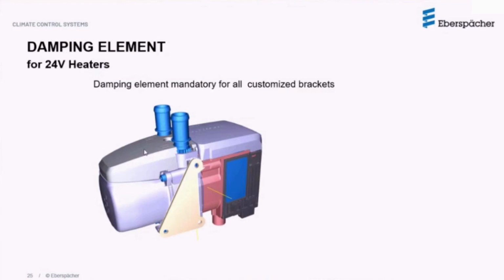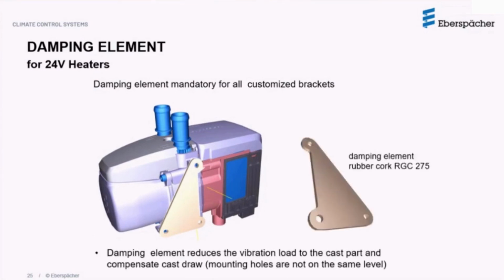With the 24-volt version of the Hydronic S3 heaters, there is what's called a damping element. This is required for all installations, and its purpose is to reduce the vibration load on the heater casing, especially when the mounting holes are not on the same level. This is a requirement and it's included in every 24-volt heater kit, so make a note of this if you're installing 24-volt heaters.